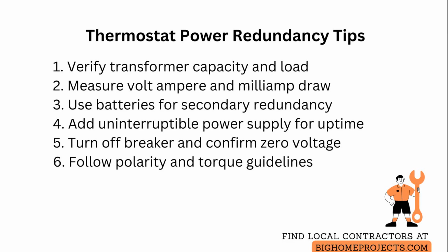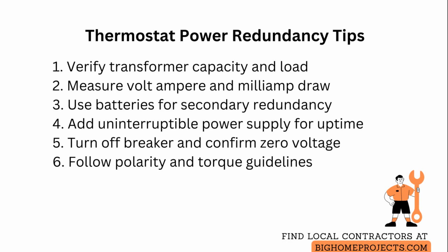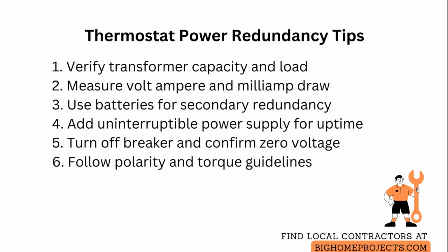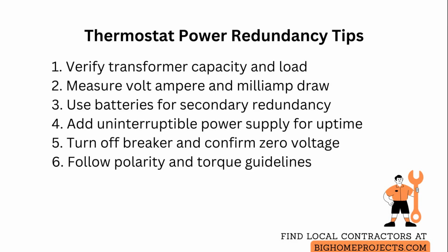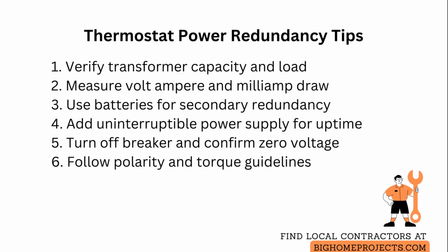Measure the transformer's volt-ampere rating and add the milliamp draw of each device to ensure a comfortable margin. If a device supports both hard wiring and batteries, use batteries as a secondary layer of redundancy to cover brief outages and to prevent resets during transformer brownouts.